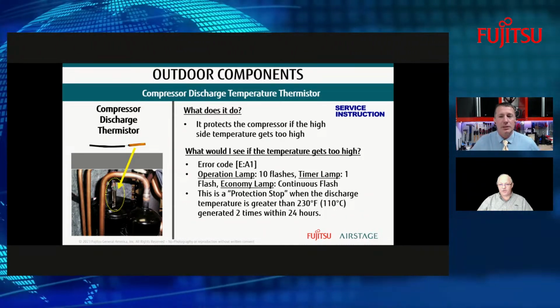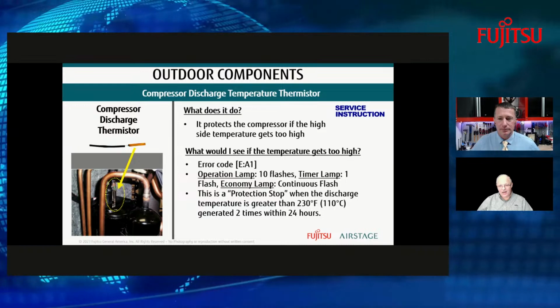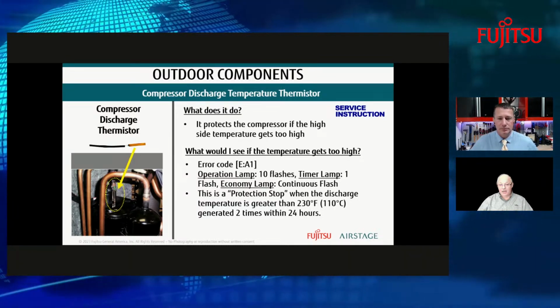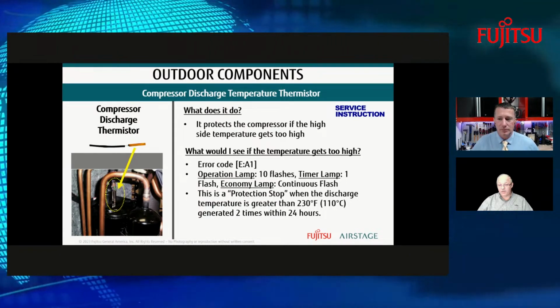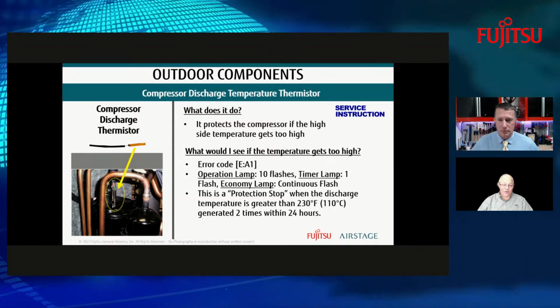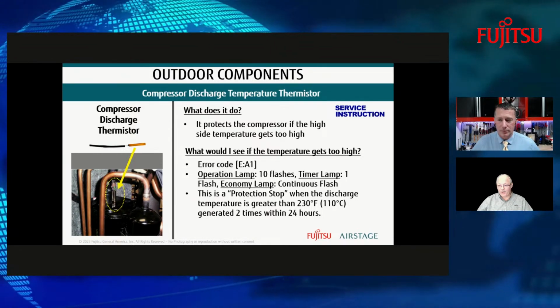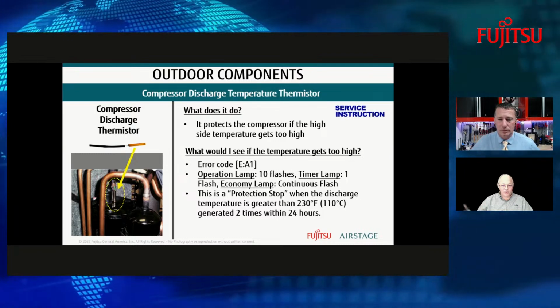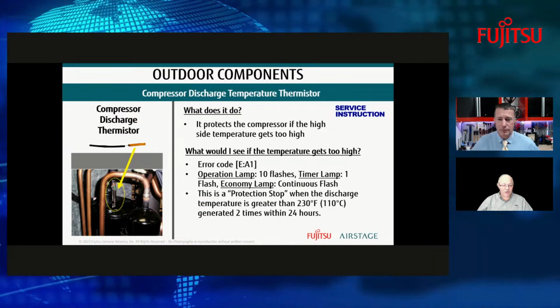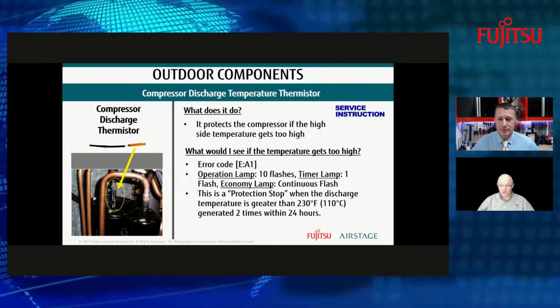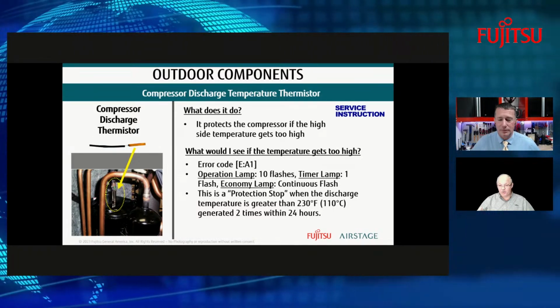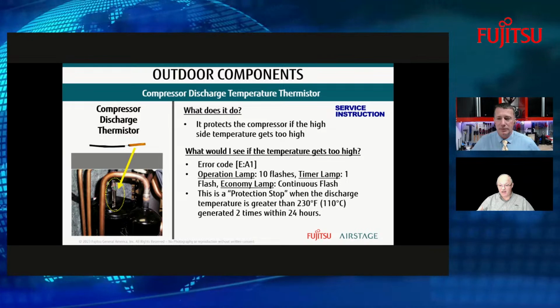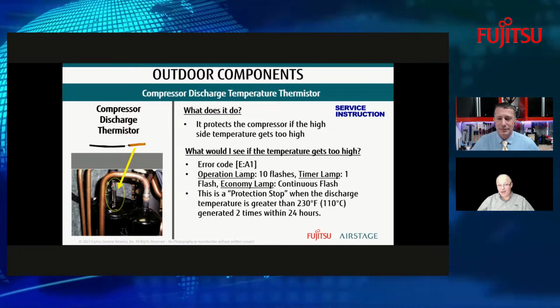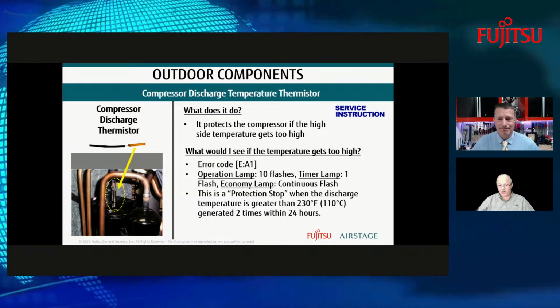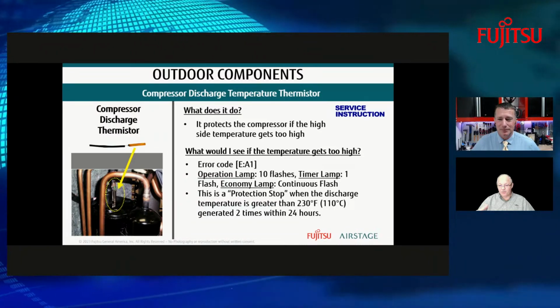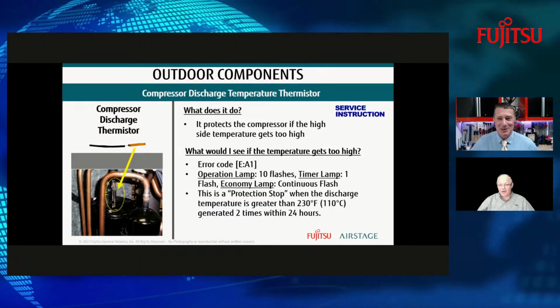We've got the compressor discharge thermistor. It protects the compressor if the high side was to get too high, and it will also generate an error code. So if there was a problem, whether that's an outdoor fan motor failure, or the bearings went out or were starting to go out and it was turning too slow, or let's just say the outdoor heat exchanger was all stopped up and dirty and needed to be cleaned, well, that could impact this compressor discharge thermistor. So we don't want the compressor to be damaged. Right. It's the most important part.